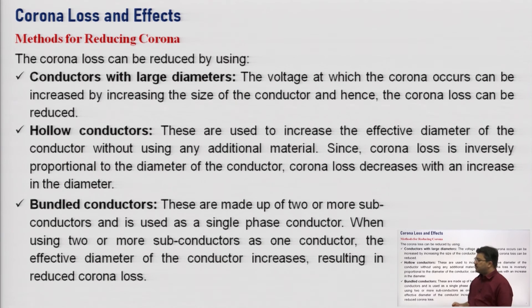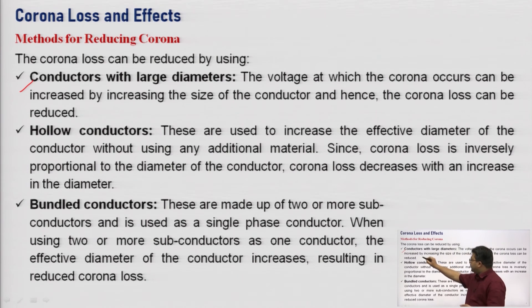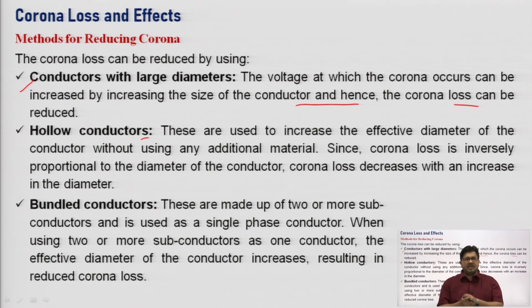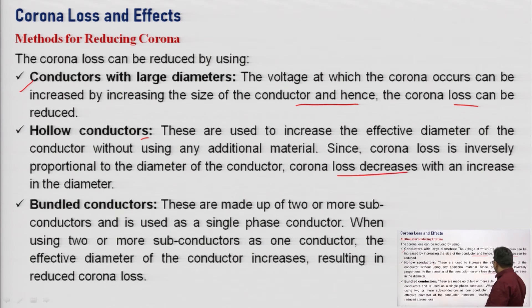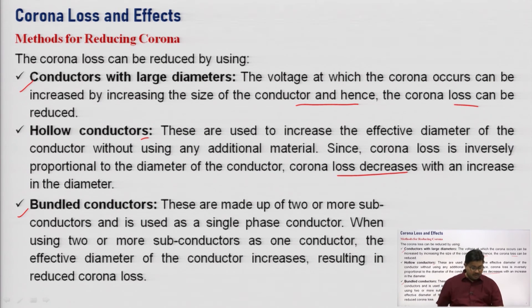To reduce corona loss: use conductors with large diameters — this increases the voltage at which corona occurs and reduces corona loss. Hollow conductors are also used to increase the effective diameter, taking advantage of the skin effect in AC systems. Using bundle conductors instead of a single conductor increases the effective GMR (geometrical mean radius), which also reduces corona loss.